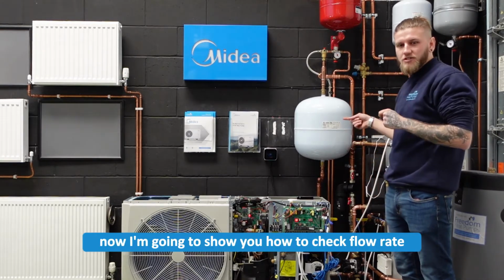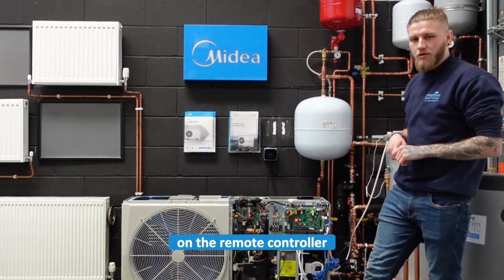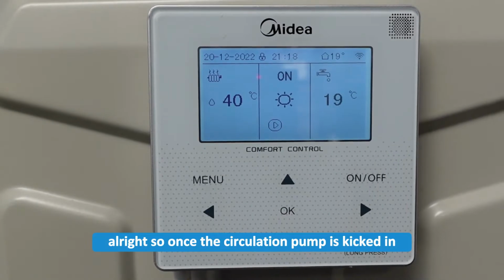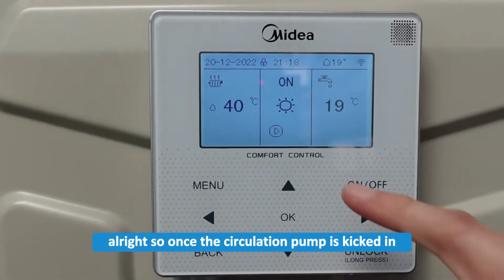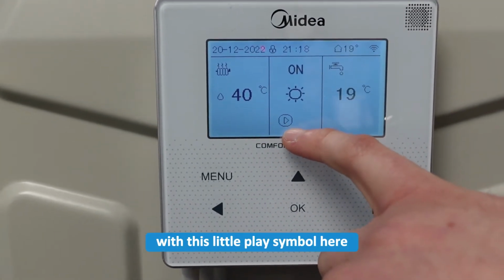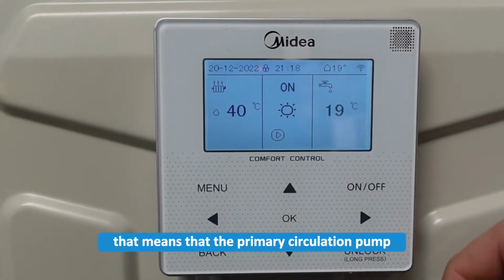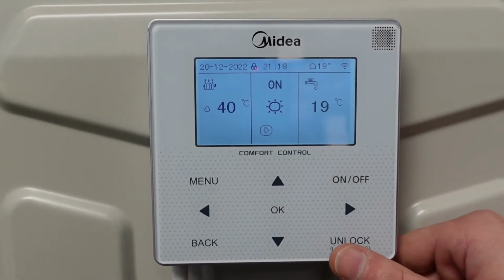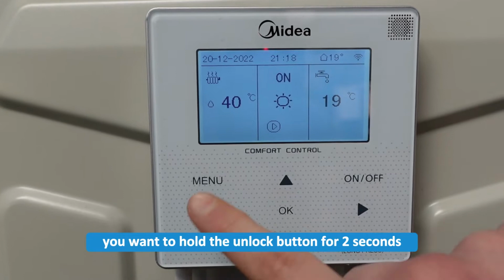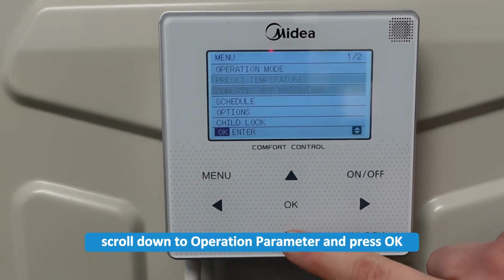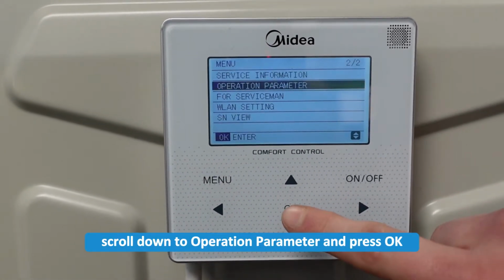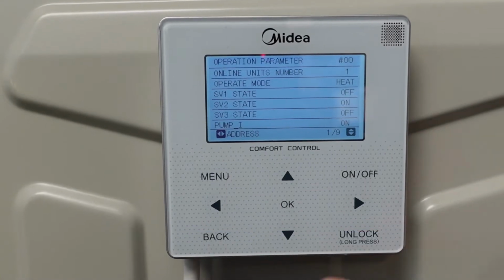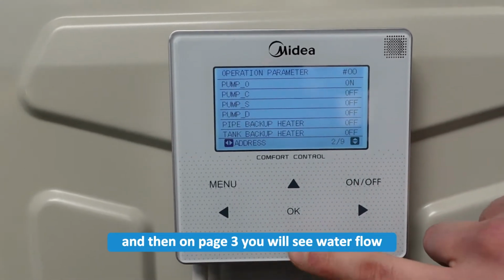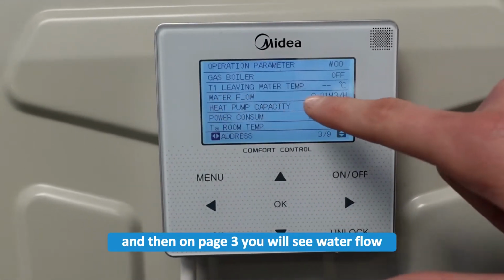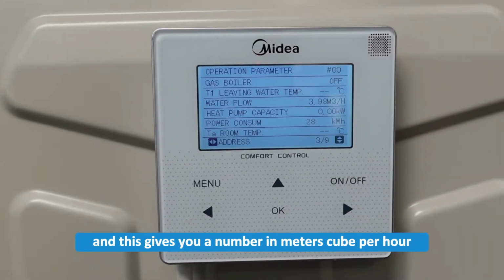Now I'm going to show you how to check flow rate on the remote controller. Alright, so once the circulation pump is kicked in, you'll be able to tell with this little play symbol here that the primary circulation pump in the heat pump is running. You want to hold the unlock button for 2 seconds, press the menu button, scroll down to operation parameter and press OK. And then on page 3, you will see water flow, and this gives you a number in meters cubed per hour.